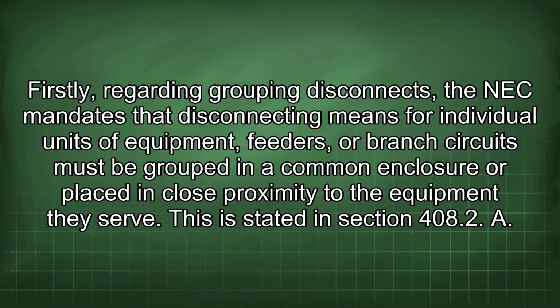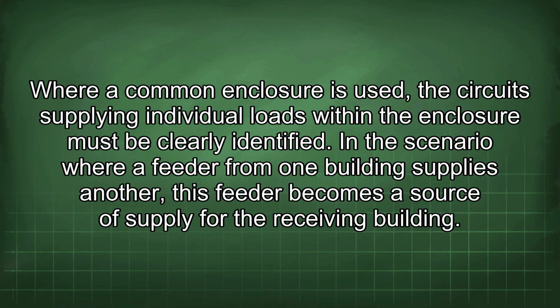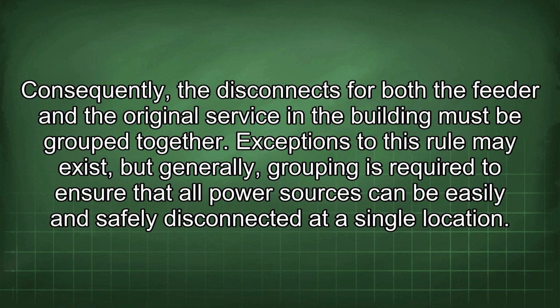This is stated in section 408.2. Where a common enclosure is used, the circuits supplying individual loads within the enclosure must be clearly identified. In the scenario where a feeder from one building supplies another, this feeder becomes a source of supply for the receiving building. Consequently, the disconnects for both the feeder and the original service in the building must be grouped together. Exceptions to this rule may exist, but generally grouping is required to ensure that all power sources can be easily and safely disconnected at a single location.